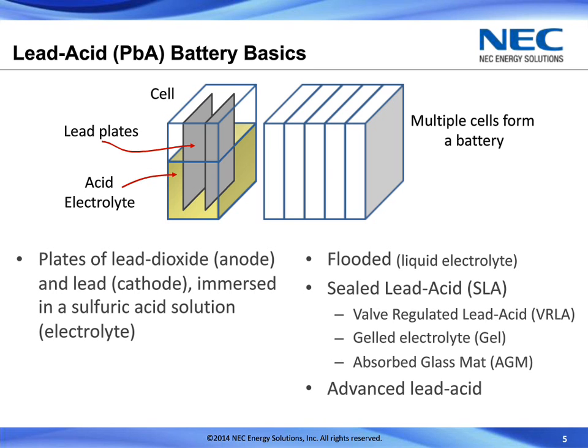That is a sealed battery that uses some sort of gel or absorbed glass mat as the electrolyte material so they don't spill, non-spillable batteries. There's some trade-off in performance to do that, but there's a wide range of different batteries available in this. And then there's a new breed of batteries often termed advanced lead acid that use different types of advancements in the type of lead that's being used or the plating to get some incremental improvements over the traditional lead acid. So this is just an overview of what's out there, and there's plenty of different technologies and product lines from various lead acid manufacturers that promise different types of capabilities for each one of those areas that are optimized.